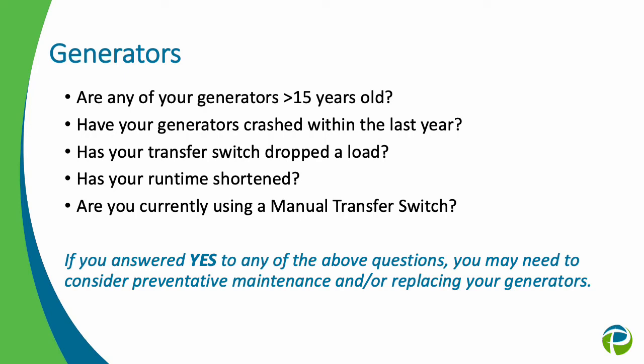But if you don't, 15 years is all you're getting. You have to look: has your generator crashed? Has your transfer switch dropped a load or not transferred correctly? A lot of times the biggest issues occur with those transfer switches, so that's definitely something we always like to look at. And then, has your runtime, if your generator is supposed to carry you for say 28 hours, is that how long it's actually carrying you? Have you had to use it that long? And also, are you currently using a manual transfer switch? We have a lot of customers who've told us they need to switch to an automatic transfer switch because the manual switch is too difficult and they have too many problems with it. So we always recommend an automatic transfer switch be used.